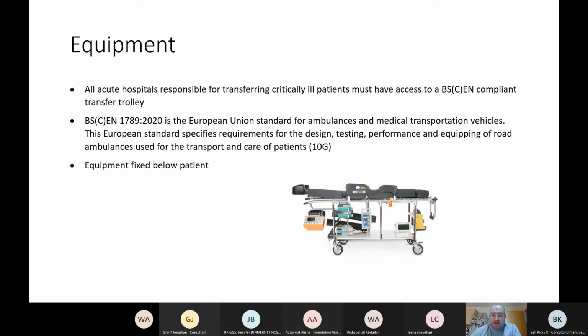You'll have probably seen it in your units or in the hospitals. It has 4 brake points on the wheels and can clip into ambulance fixation points between the wheels, and that trolley is tested to 10 Gs of force, which means that it's very stable. It has secure places for oxygen cylinders. There was a terrible case prior to use of these sorts of trolleys in the Manchester area where somebody sitting behind the driver in an ambulance was killed by a projectile oxygen cylinder.